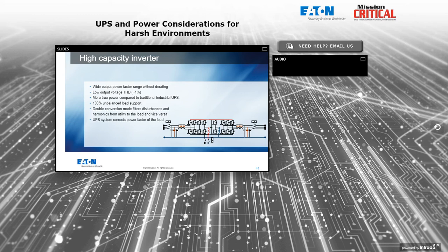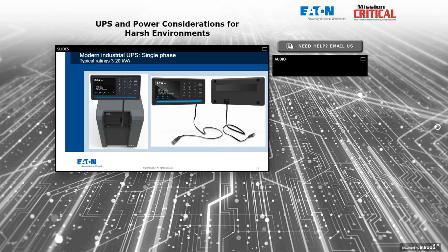The UPS system should also act to correct low power factors for the critical load, so that the UPS would typically have the ability to correct for low power factors, even if it's in high efficiency mode, for example. And the way it does that is the UPS can be set up to act like a set of noise canceling headphones, where we sense the harmonic presence and the power factor of the load and take action electronically to correct that, like an active power factor corrector, which is a commonly seen device in industrial applications, whether it is a UPS system or not.